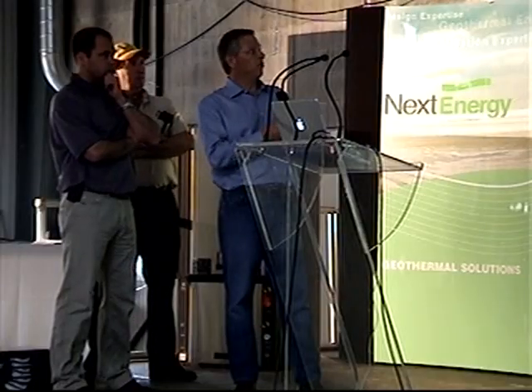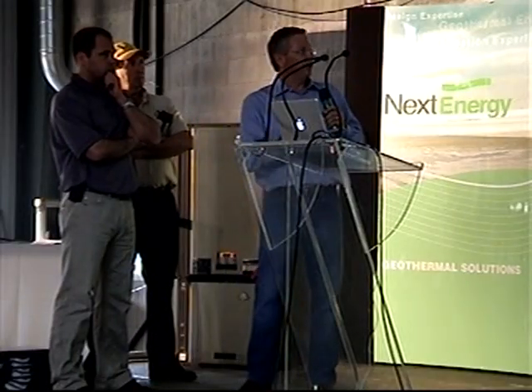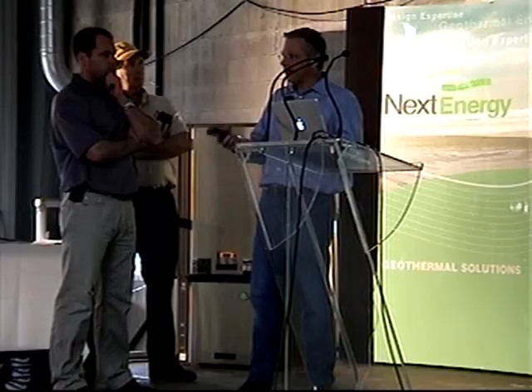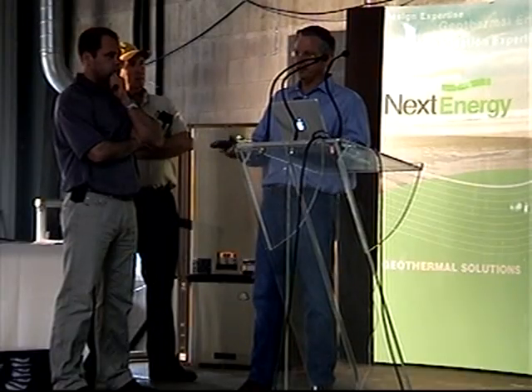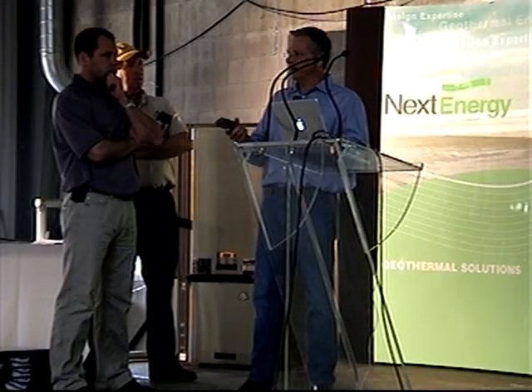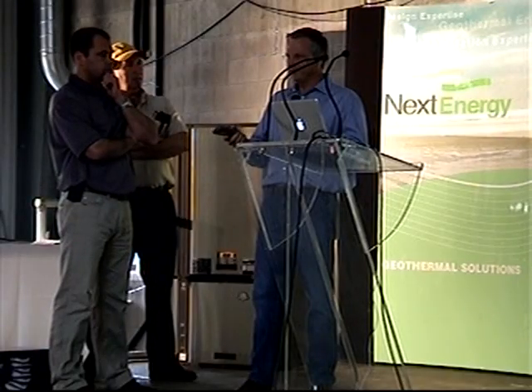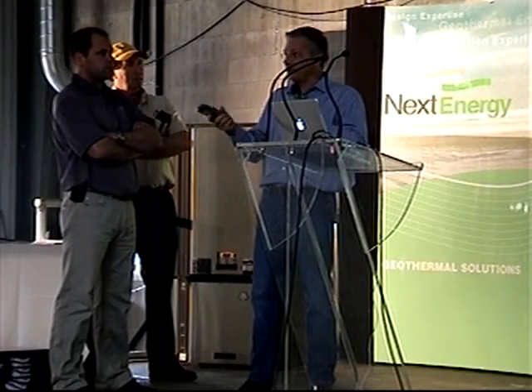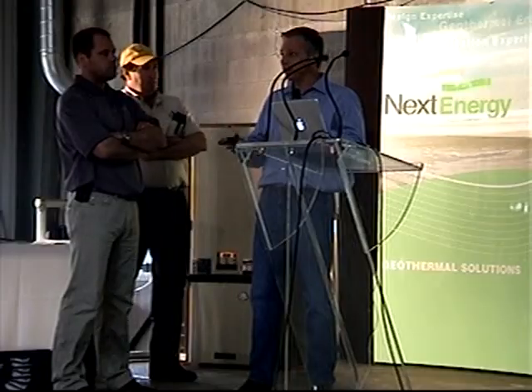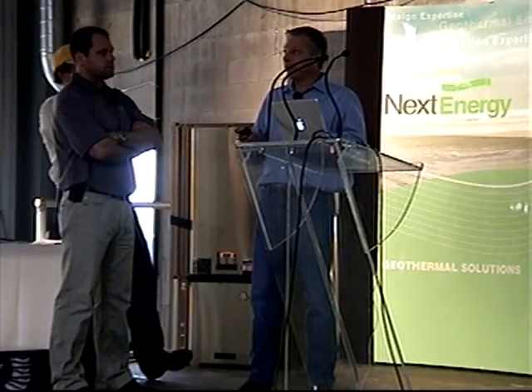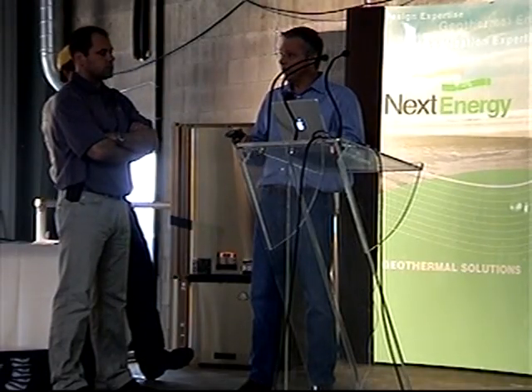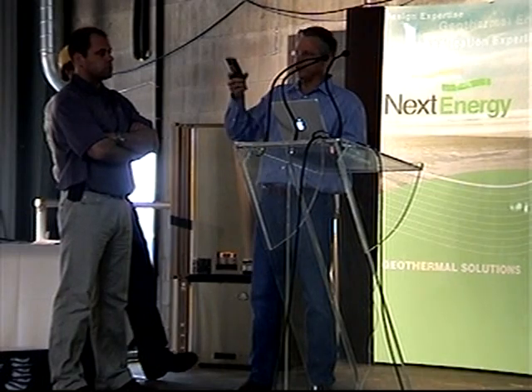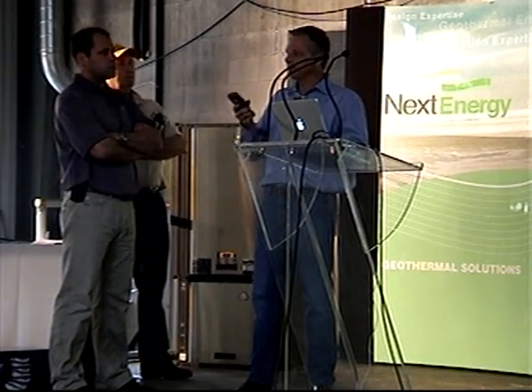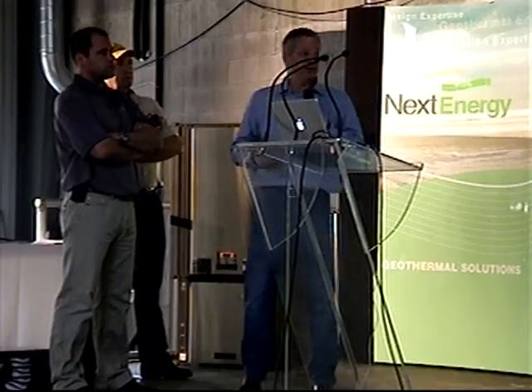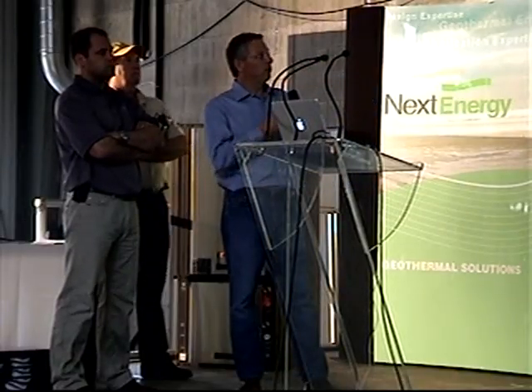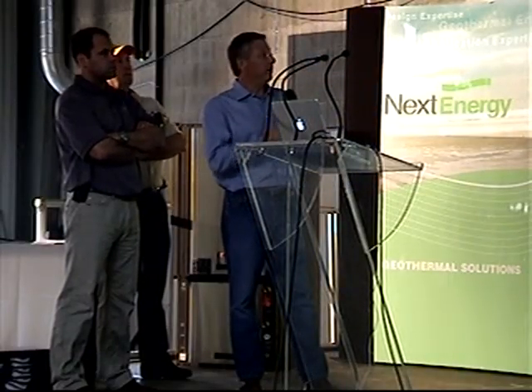One of them is the unit performance sentinel. If there's a problem with the system, but it's not locked out, it's just not running efficiently, it'll actually blink and let the homeowner know that something's up. They may call you and you say, what's it doing? They say, well, it's blinking kind of slow. You say, oh, well, it could be anything from a dirty filter. Basically what it's sensing is that the condensing and evaporating temperatures are not normal for the unit. And I'm assuming it's going to get into more detail on that as we get into this show.